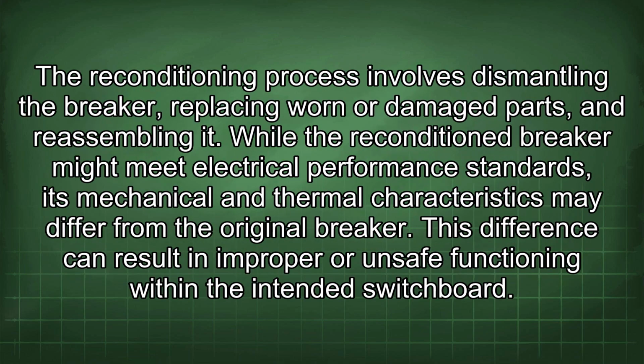The reconditioning process involves dismantling the breaker, replacing worn or damaged parts, and reassembling it. While the reconditioned breaker might meet electrical performance standards, its mechanical and thermal characteristics may differ from the original breaker. This difference can result in improper or unsafe functioning within the intended switchboard.